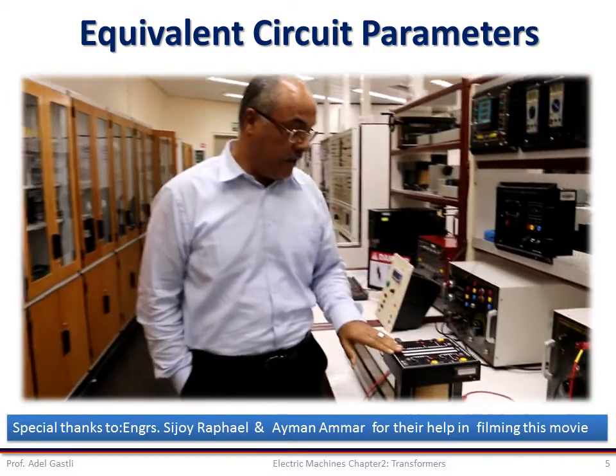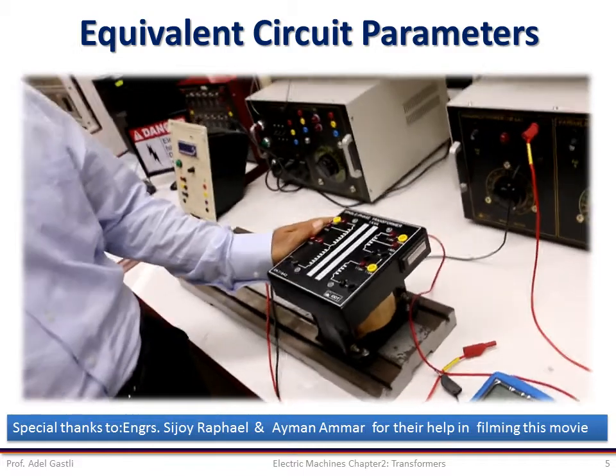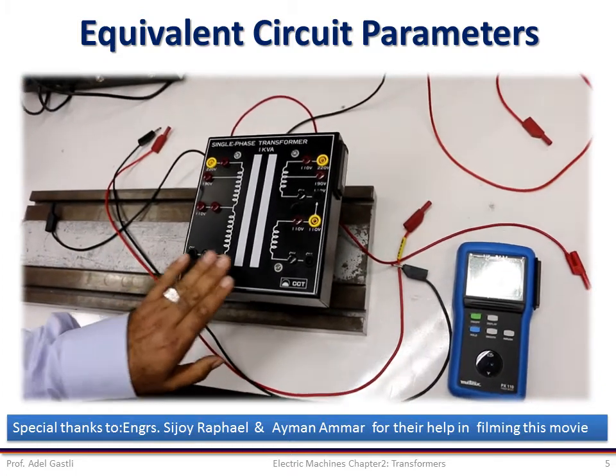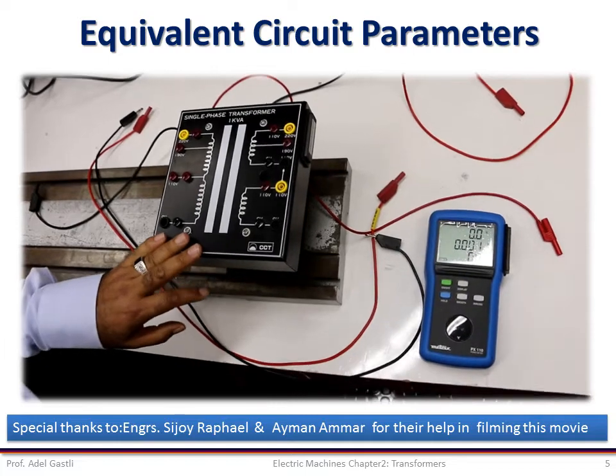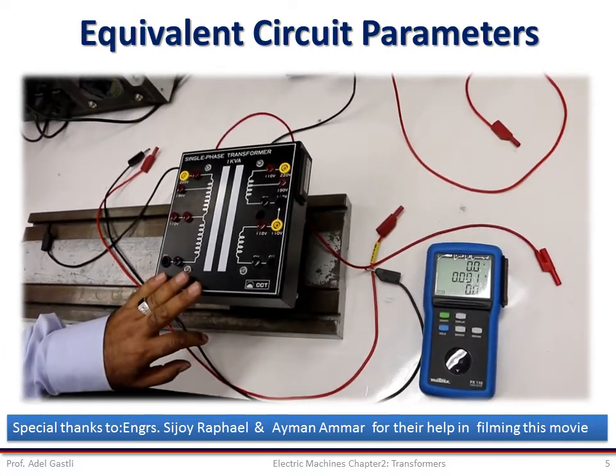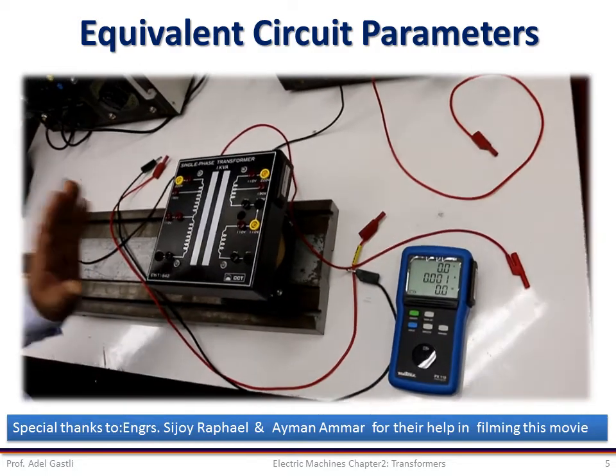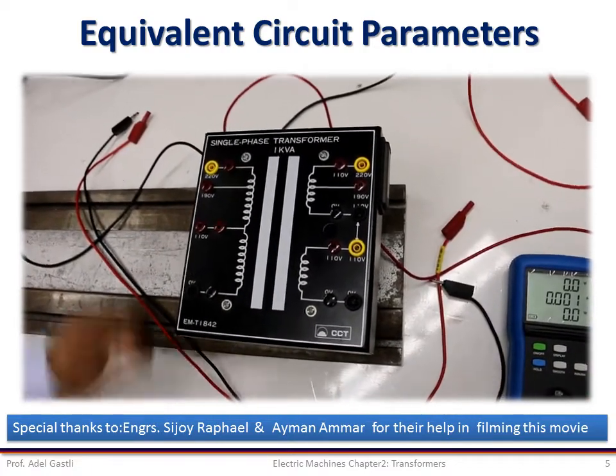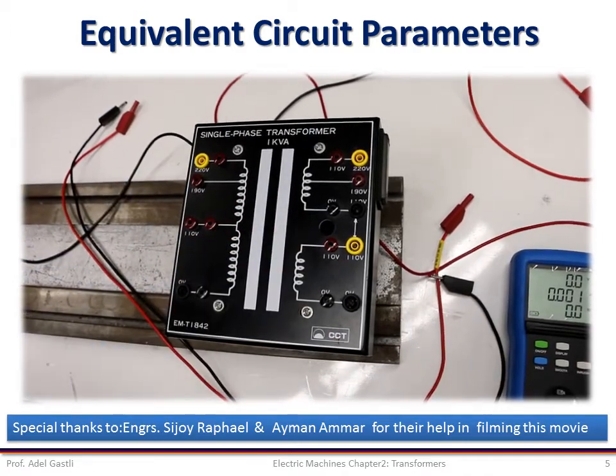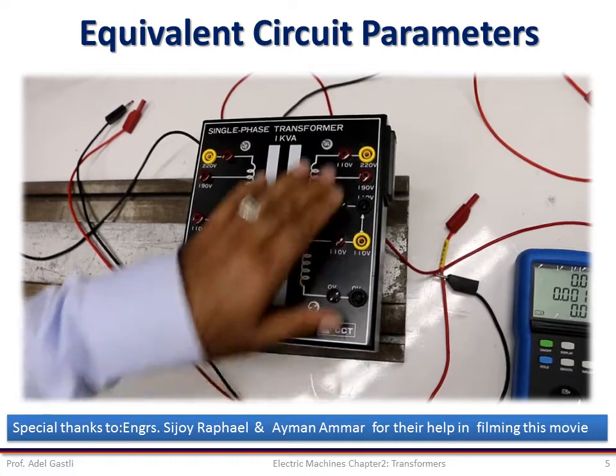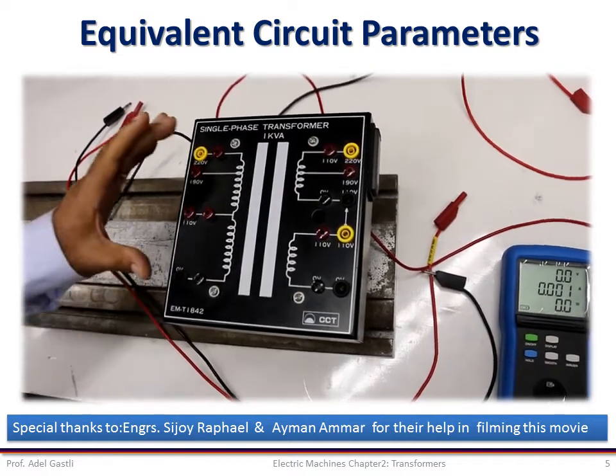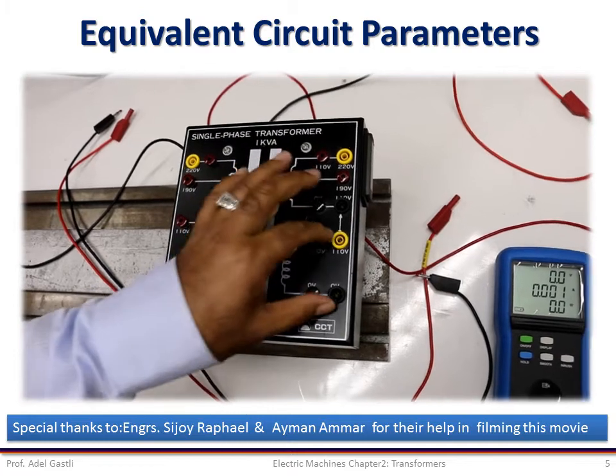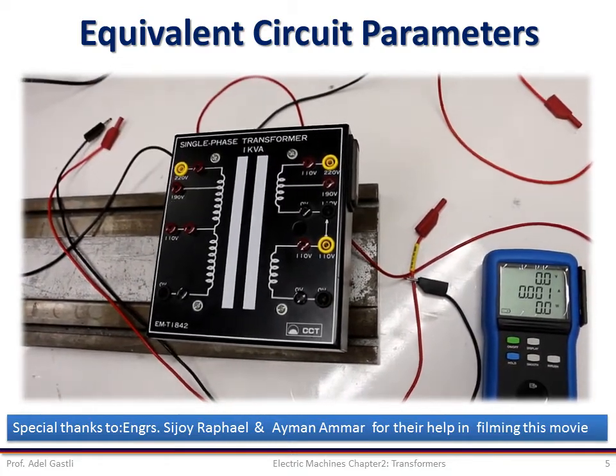Today we're going to talk about the open circuit test and the short circuit test on the transformer. We're going to take one single phase transformer and show how we can run the experiments to calculate the equivalent circuit parameters. Before starting, we look at the nameplate, which has all the information related to power, input voltage, and output voltage. Here we have a single phase transformer with two windings in the secondary. We're going to take only one winding; our voltage supply will be 220 volts, the output in the secondary will be 110 volts, and the power is 1 kilovolt amp.